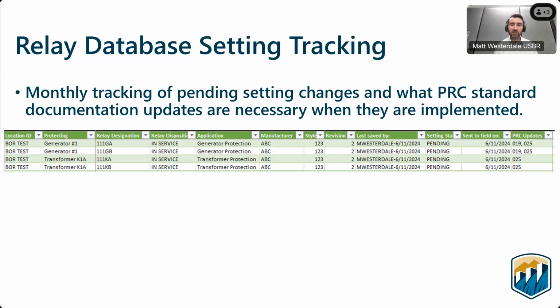As I mentioned, we made updates to the 51 elements and 21 elements, so that falls under the scope of PRC 25. Once we're notified those settings are implemented, this allows us to do a quality check to make sure things don't fall through the cracks, and we update our PRC 25 documentation as well.